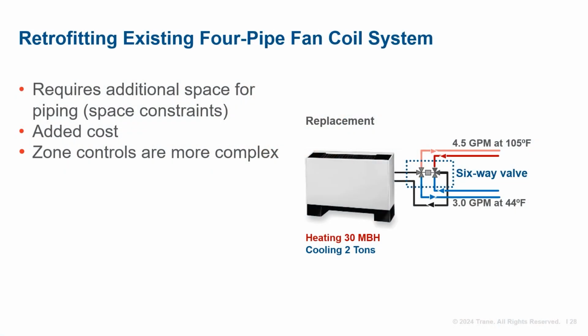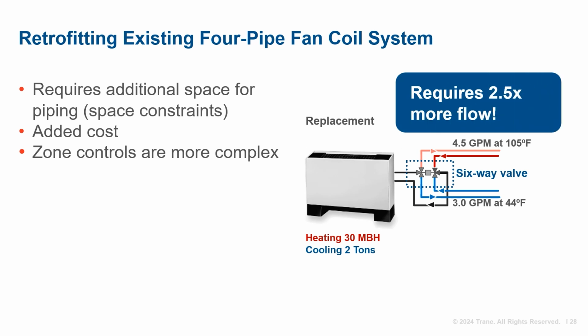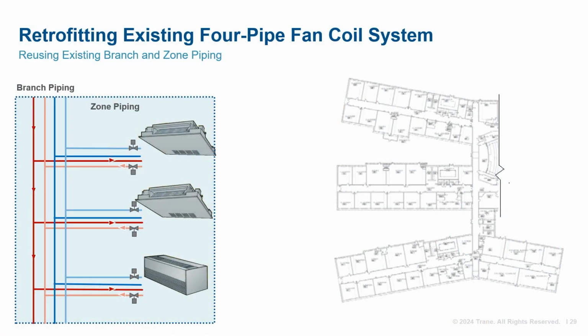If one can find space to incorporate the 6-way control valve option, there's another issue that arises: the distribution piping. Changing from 140-degree supply hot water to 105 degrees requires 2.5 times more flow in our example system. That means new branch and zone hot water piping will be required to make this option work. In retrofit scenarios, there is an alternative solution that may be applicable in some cases.